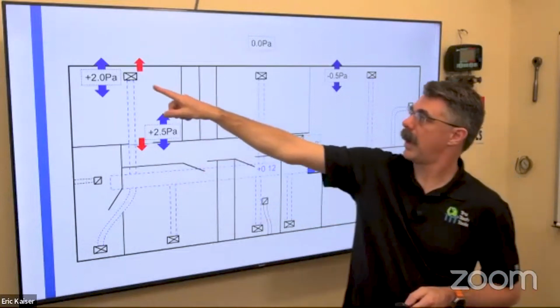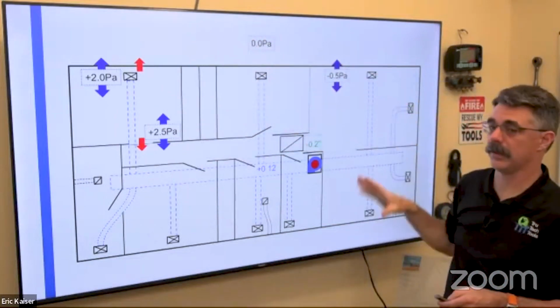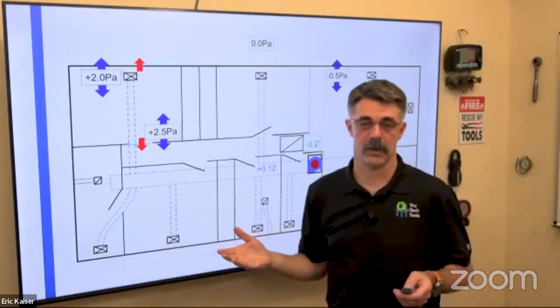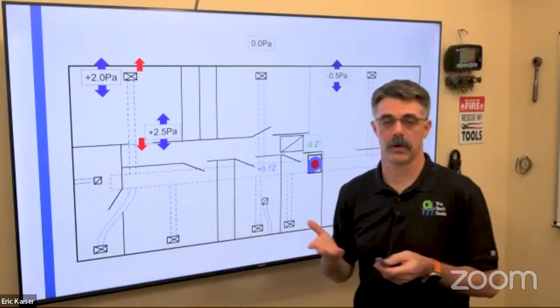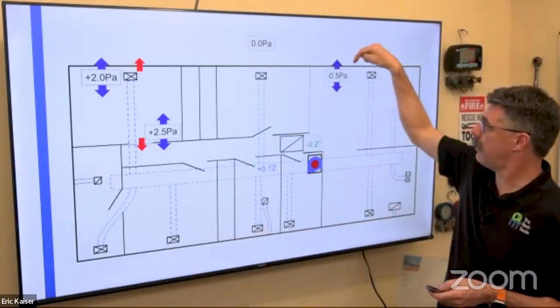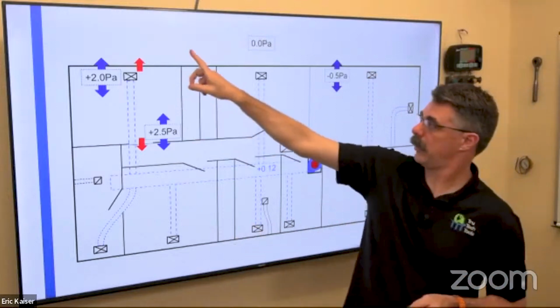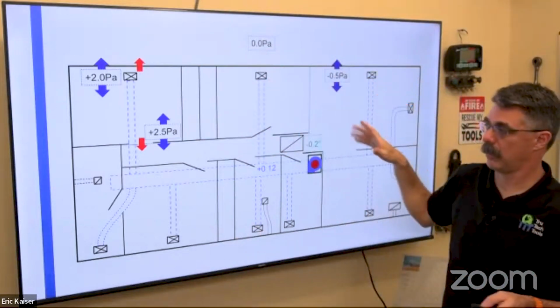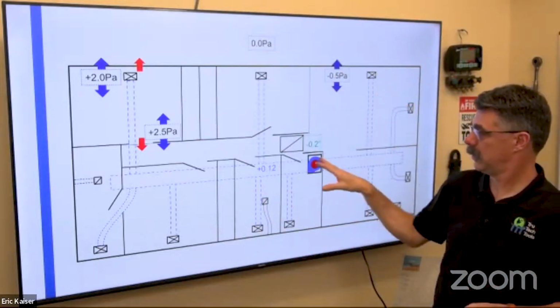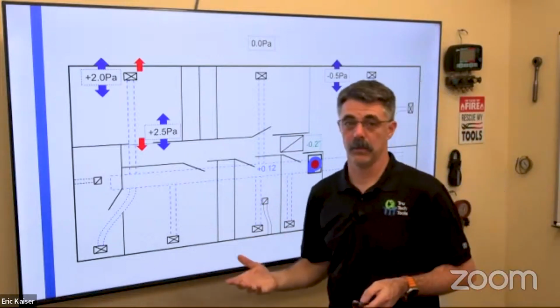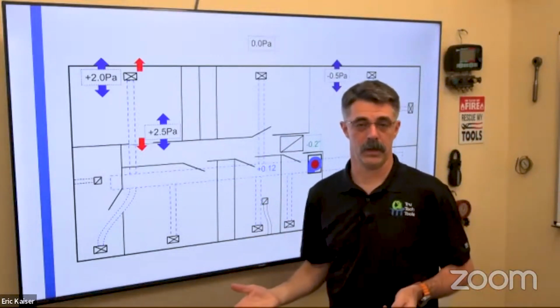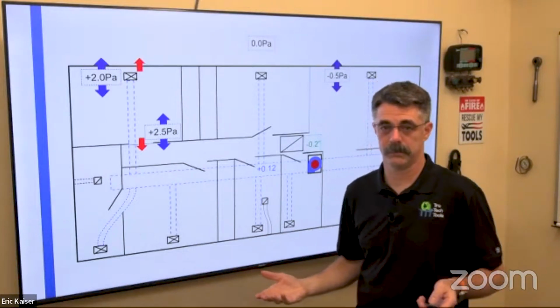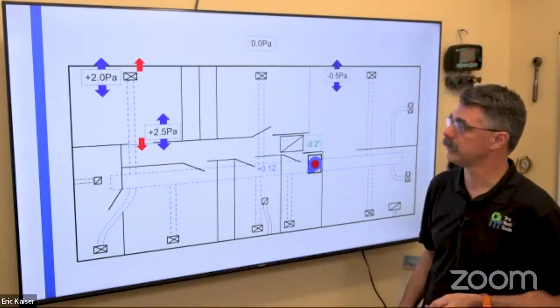Well, if it leaks out of the house, then it's got to come back in, because everything has to equal out eventually. Pressure seeks a level. So it's going to come back in over here. So we're blowing air out of this room, and we're bringing air back in somewhere else in the house to bring it back to the air handler, because the air handler is going to move the same amount of air no matter what. It really doesn't care where it comes from. So we'd like to control that.